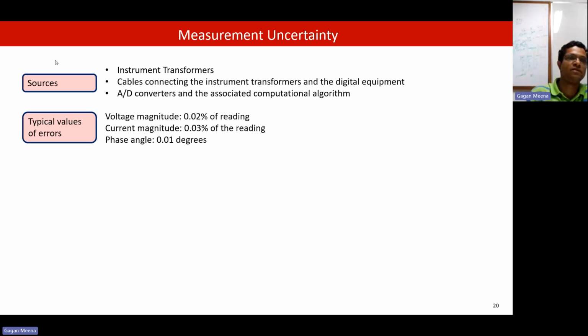And these are the different measurement uncertainties in PMU. The sources of these measurement uncertainties first come from the instrument transformer because of the calibration problem. Then from the cable which connects the instrument transformer and the digital equipment. Last are the AD converters and the associated computational algorithm.